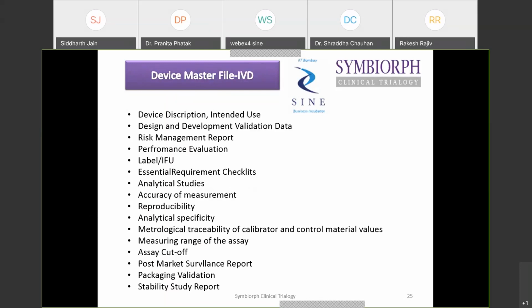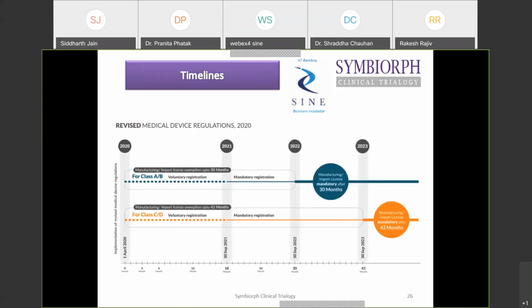Now, if your device falls under in vitro diagnostic medical devices, then you again have to prepare the risk management, performance evaluation data, and analytical studies, accuracy of measurement, reproducibility data, assay cutoff. All this type of data you have to submit in detail, and it is going to be audited by the notified body for the release of the manufacturing license. Now, what are the timelines?